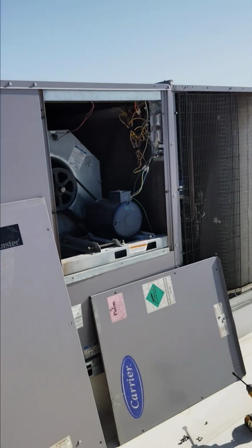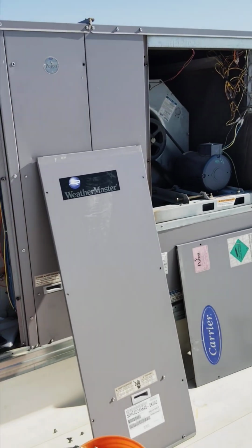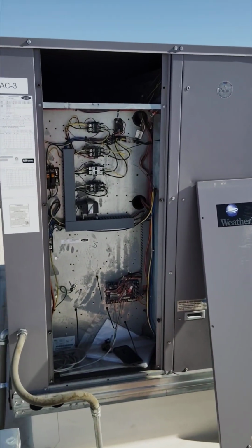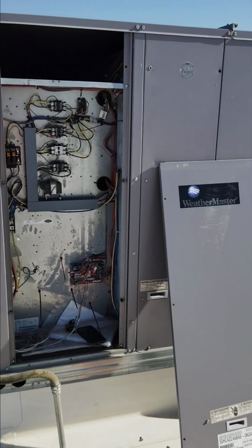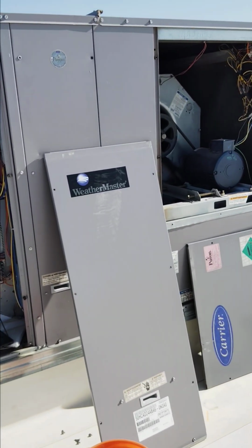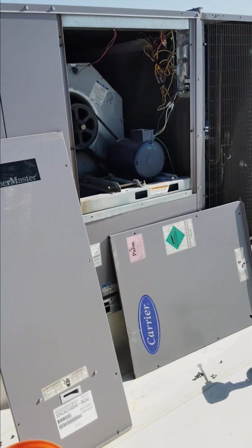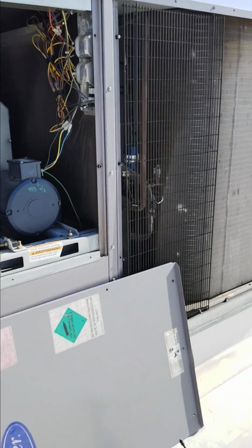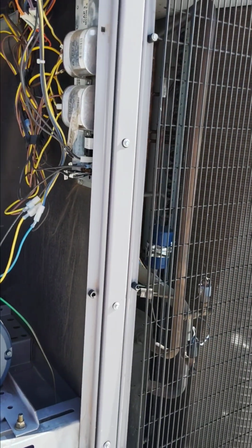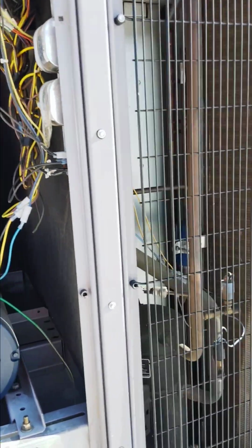So you check high voltage, make sure everything is tight on the connections for the contactors, and make sure that all the connections are not rubbing and everything is tight. Check the amp draws, voltage, and you check the bearings to make sure you don't have any play.